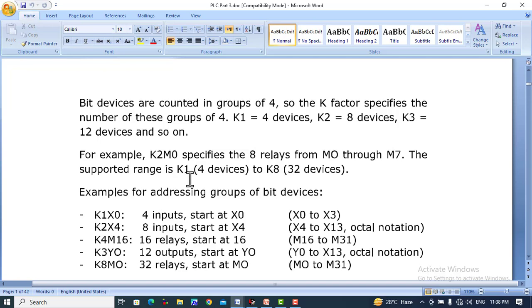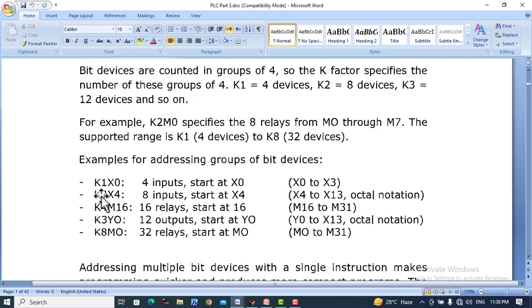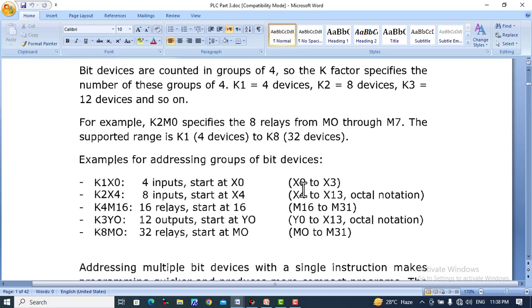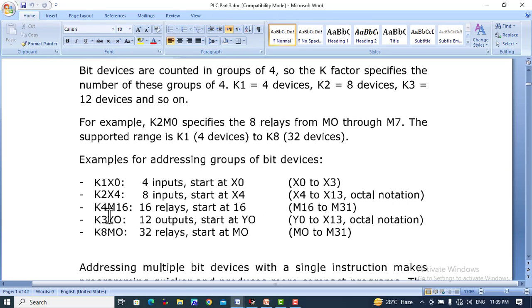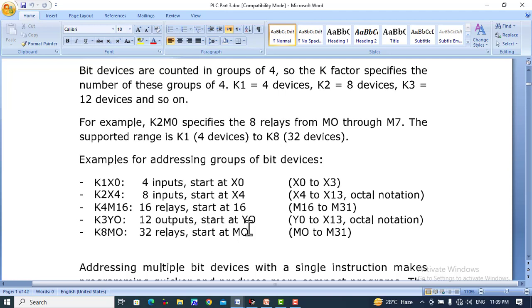For example, K2 M0 specifies eight relays from M0 to M7. The supported range is K1 (four devices) to K8 (32 devices). K1 X0 means four inputs from X0 to X3. K2 X4 means eight inputs starting at X4, from X4 to X13 in octal notation. K4 M16 takes 16 relays from M16 to M31. K3 Y0 takes twelve outputs from Y0 to Y13. K8 M0 takes 32 relays from M0 to M31.